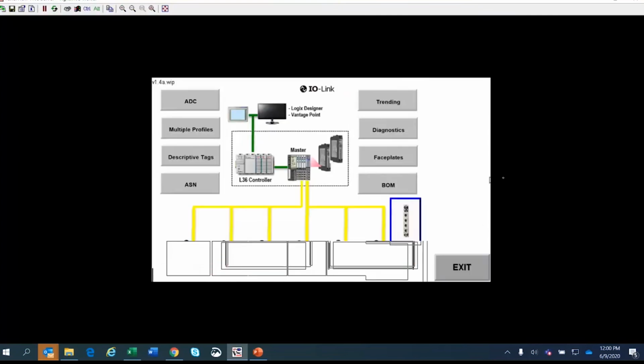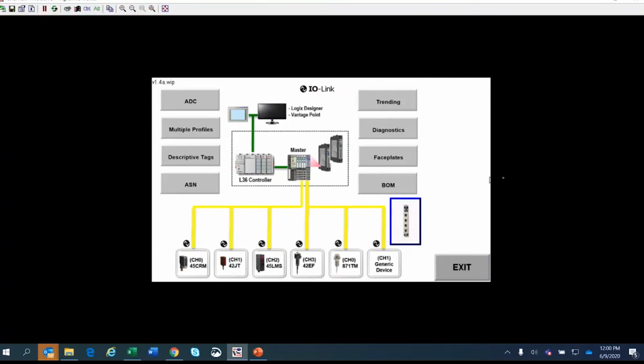I have set this up so that if you see something at about 1 foot, I'm at about 1 foot from the sensor, 300 millimeters, one of the outputs is on. There's another virtual output in there that if you see something at 2 feet, now I'm at about 2 feet, and another output is turning on. You can create multiple windows, and get multiple virtual outputs. Now we have added functionality. You can do more things with the sensors with having done that. So the first part was the preventive maintenance part of it. I'll go on to performance features, enhanced performance, as we go along later.